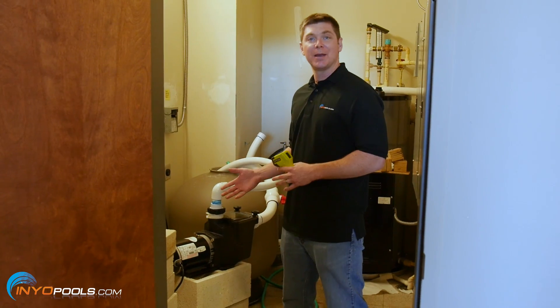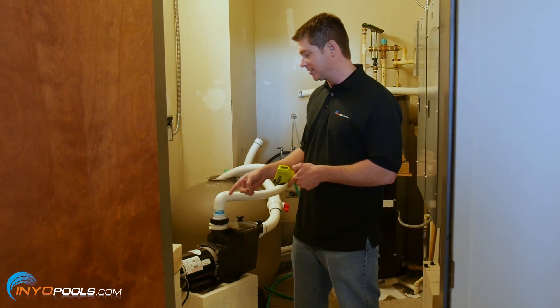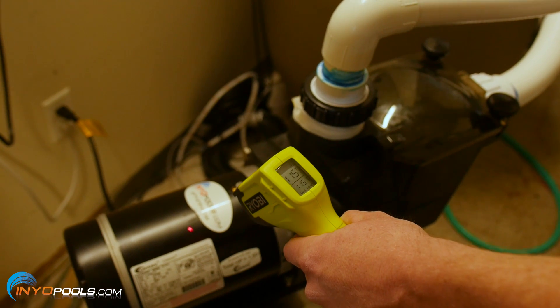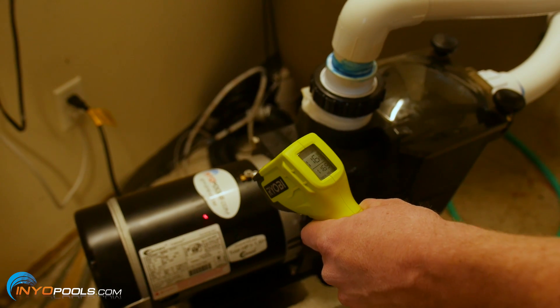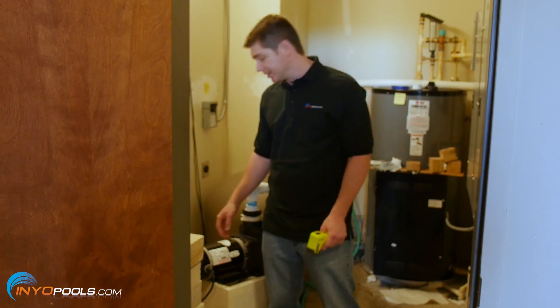This week we wanted to take you behind the scenes and show you a little bit of our testing. We're back here at one of our testing stations. We've got our infrared thermometer and we're going to check to see how hot this one is. This is in an air-conditioned environment, so we'll see what it's coming out at. This motor's been on for about an hour — it's running about 115 degrees. Obviously, if this were out in the sun, it'd be much higher. But to basically sum it all up, yeah, these motors run hot.